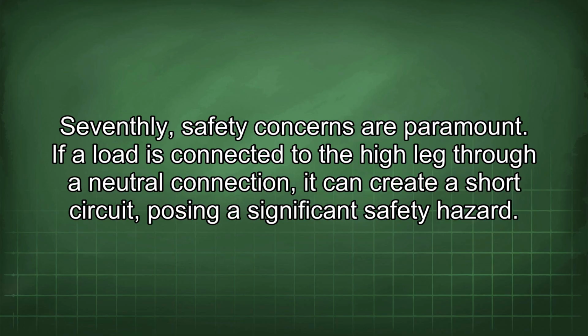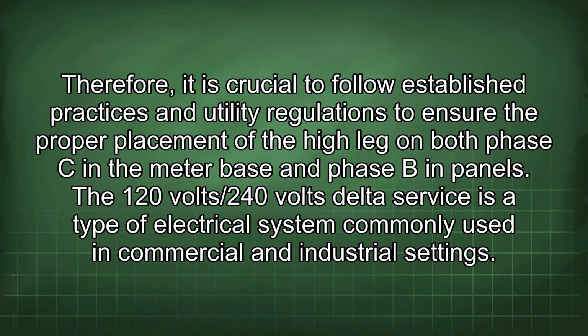If a load is connected to the high leg through a neutral connection, it can create a short circuit, posing a significant safety hazard. Therefore, it is crucial to follow established practices and utility regulations to ensure the proper placement of the high leg on both phase C in the meter base and phase B in panels.